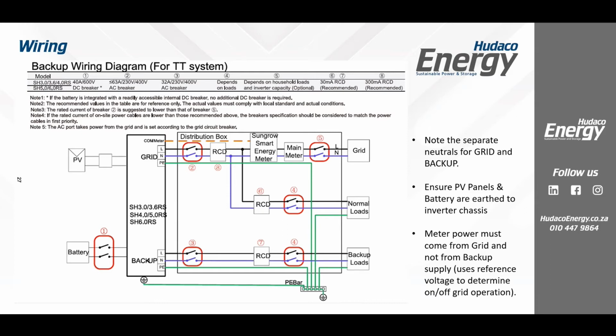Okay. So this here is where you will put your feed, sorry, Graham. An RCD is a residual current device, also known as earth leakage, more commonly. What it does is it detects if there's potentially a break in a cable somewhere or an exposed amount of energy that can flow through the earth or through a wall. Yeah, earth leakage. And that will trip to prevent anyone from getting injured. Okay, so then we've got our feed to the inverter, and this is our grid port on the inverter. Right? Then we've got our PV coming in. Please note we need to bond. Now this doesn't show here, but we do need to bond the battery and PV ports via earth, right? There are connection points on the chassis of the inverter. Please make sure you bond them properly.